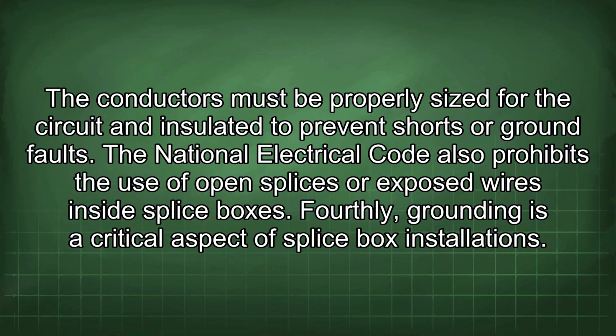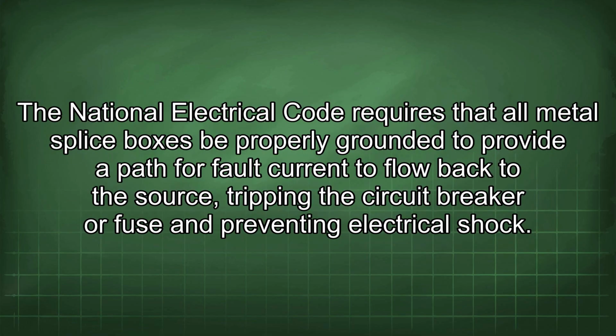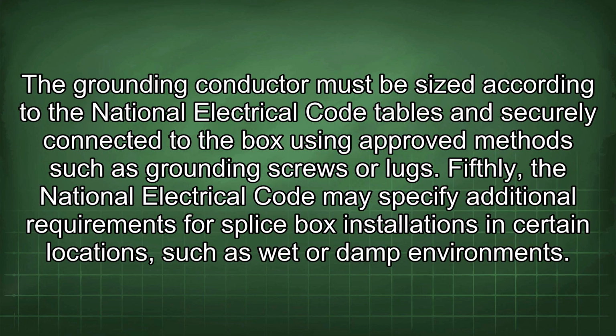Fourthly, grounding is a critical aspect of splice box installations. The National Electrical Code requires that all metal splice boxes be properly grounded to provide a path for fault current to flow back to the source, tripping the circuit breaker or fuse and preventing electrical shock. The grounding conductor must be sized according to the National Electrical Code tables and securely connected to the box using approved methods such as grounding screws or lugs.